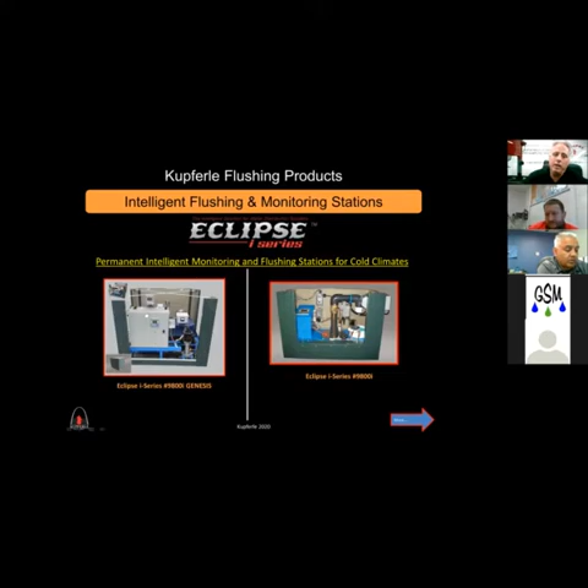It creates its own power using a water turbine and a battery bank. So with this one, I don't need any 120 line power or solar. It has a 24 VDC battery bank in the enclosure, and the water turbine charges the batteries, runs the heater, and operates the station year-round right off the power of the moving water in the main. The nice thing is I can put it anywhere I want, since the main is my power source—I don't need a southern exposure or proximity to 120 line power.